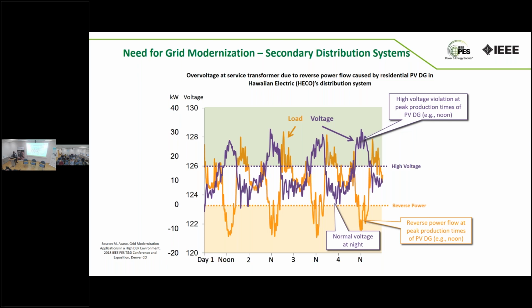The purple line shows that during noon it's completely correlated with the reverse power flow from that service transformer, voltage exceeds that limit.